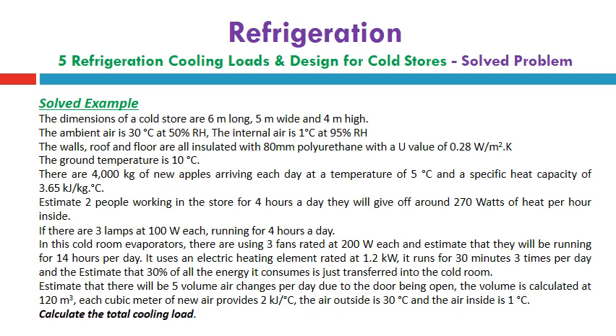Finally, in this slide, we will present a solved example for a refrigerated cold store under design, to estimate the total cooling load required for this room. The dimensions of the cold store are 6 meters long, 5 meters wide, and 4 meters high. The ambient air is 30 degrees Celsius at 50% relative humidity. However, the internal air is 1 degree Celsius at 95% relative humidity. The walls, roof, and floor are insulated with 80 millimeter polyurethane with a U value of 0.28 watt per meter square Kelvin. The ground temperature is 10 degrees Celsius.